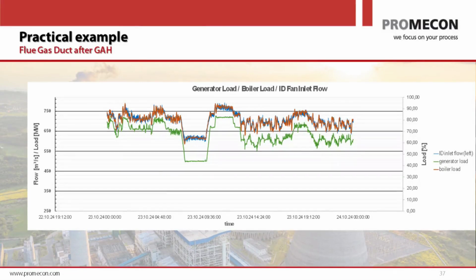And here you can see a typical example of flue gas measurement. ID inlet flows, that's what we usually do. And yeah, in this case, it was fairly okay, but we have also seen ID fan flows, which are different by 1%, 1.5%, or even 2%. And for a total gas flow out of the boiler, 2% is a lot. That's not a small number. And we've been helping a lot of power stations around the world to optimize their flue gas flow out of the boiler.